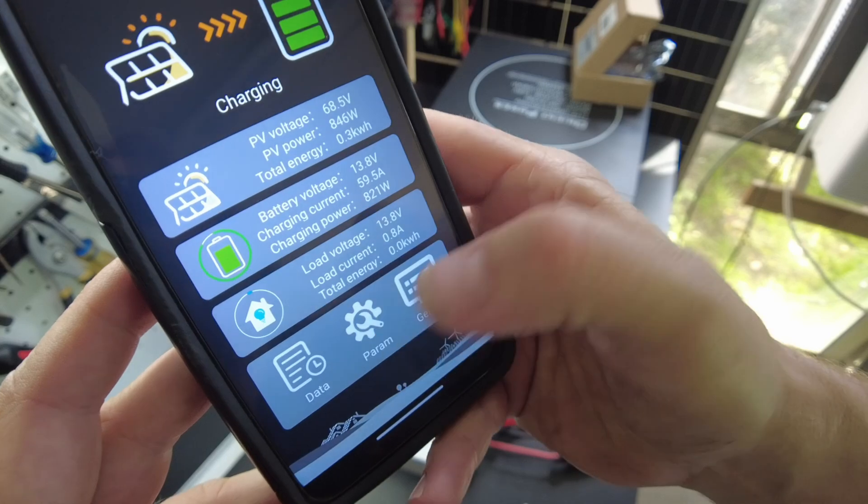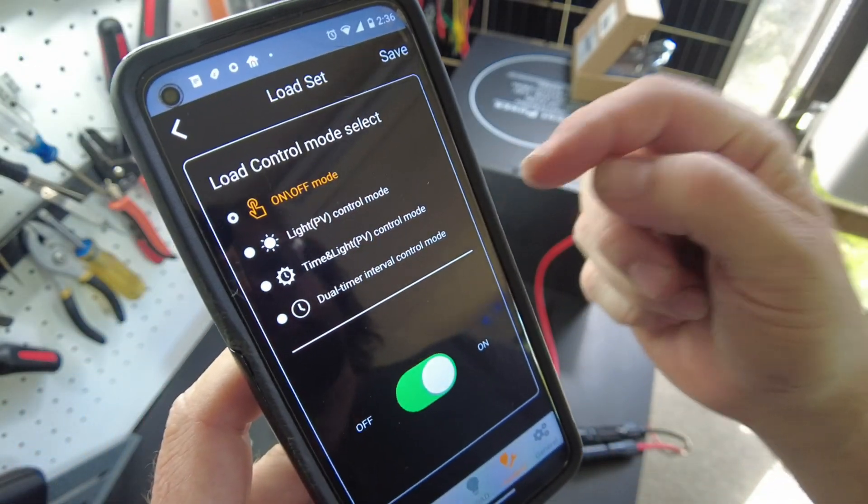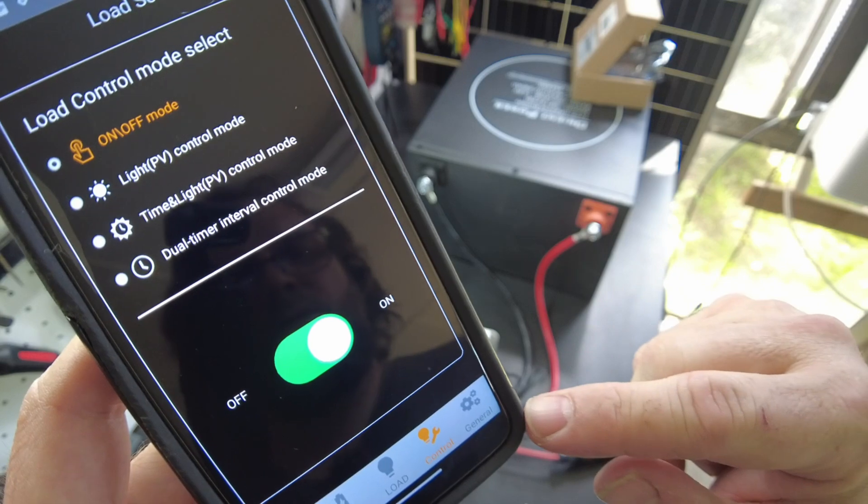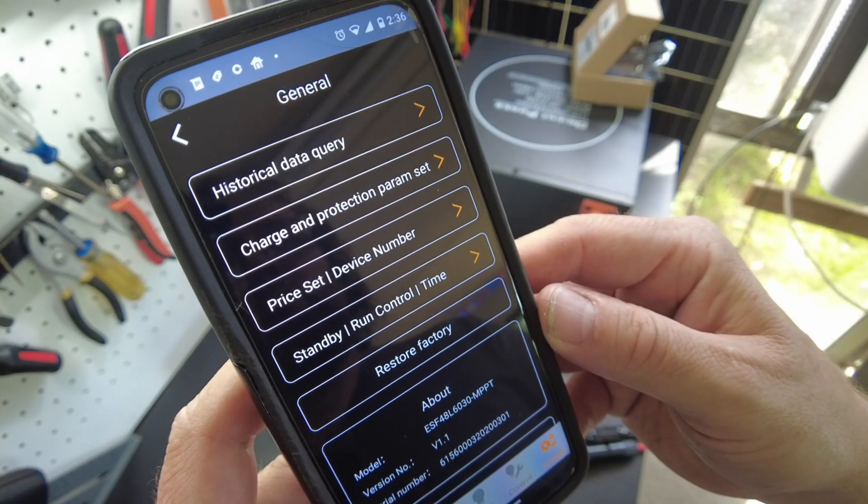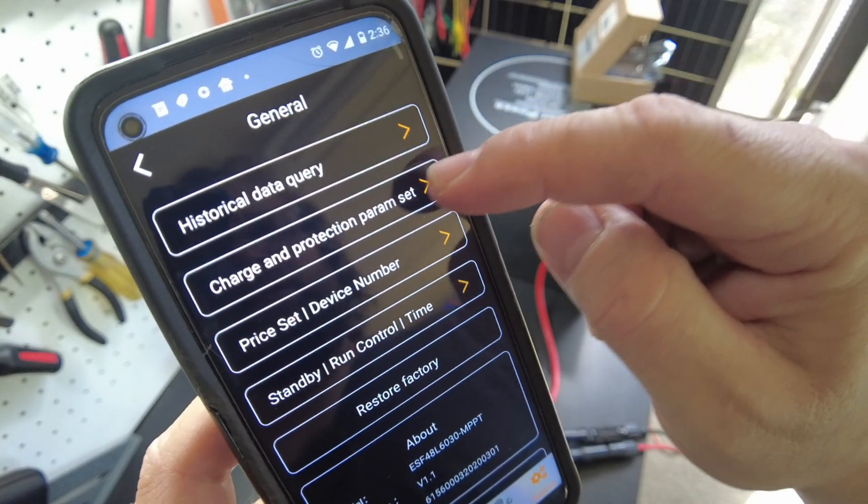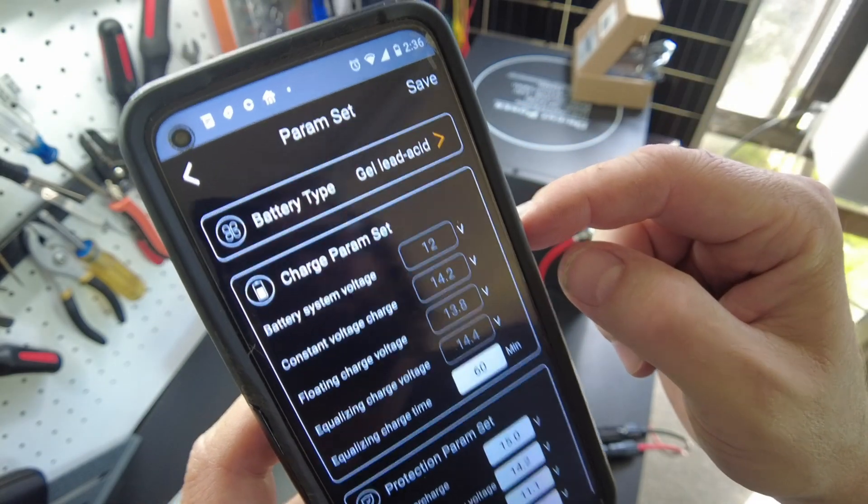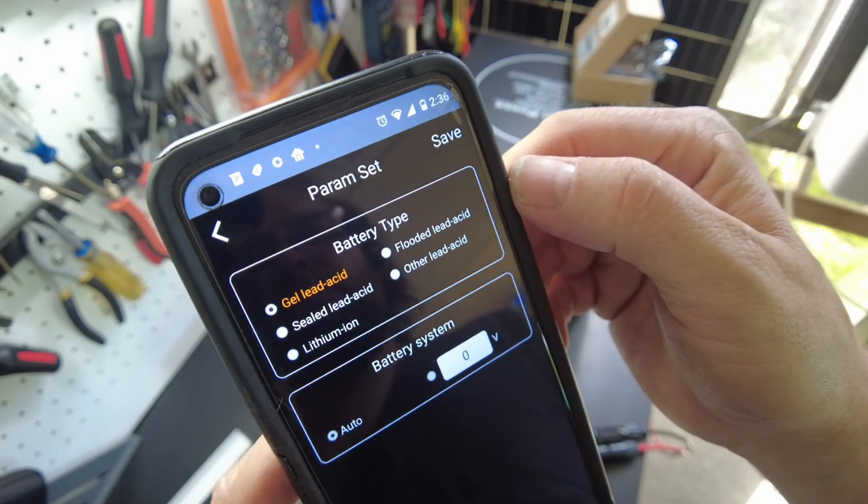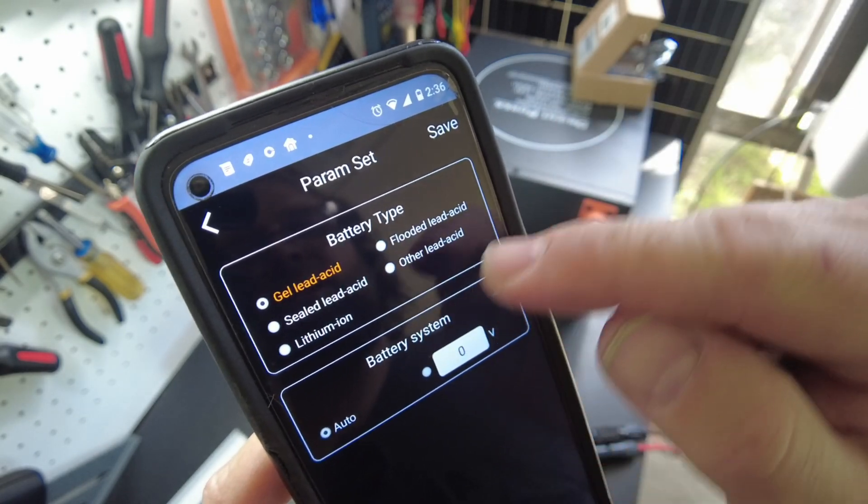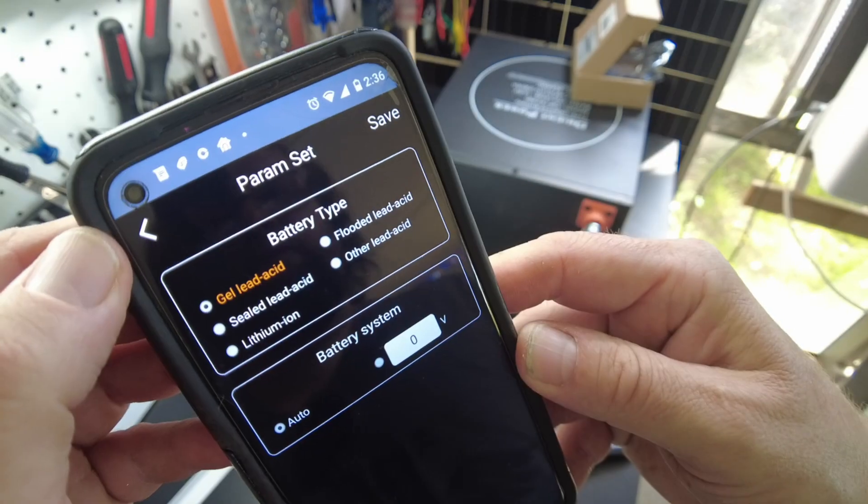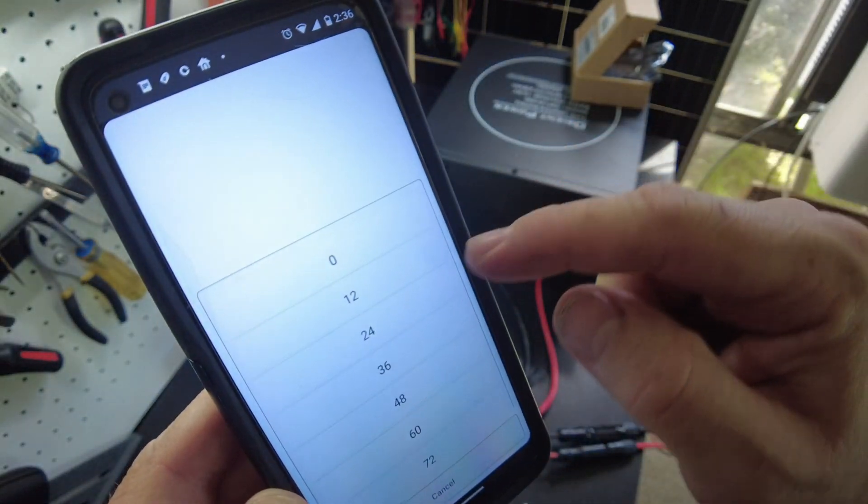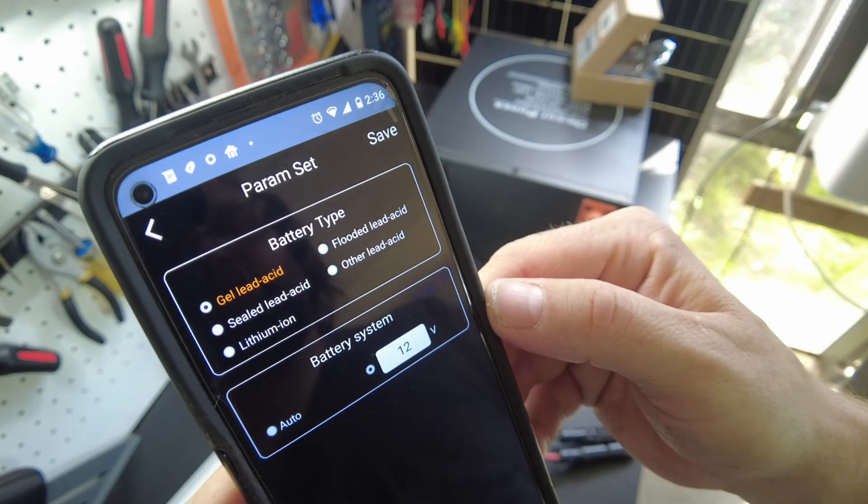All right. So this is like our load control. General. Okay. Here's our charge and protection parameter set. Okay. So this is where we can change our battery type. We can do lithium ion, sealed lead acid, flooded lead acid, other lead acid. Okay. So it's on auto. I don't like that usually. So let's do that. It has a 12 volt system. Save that.